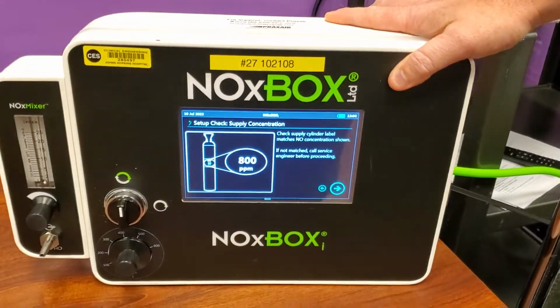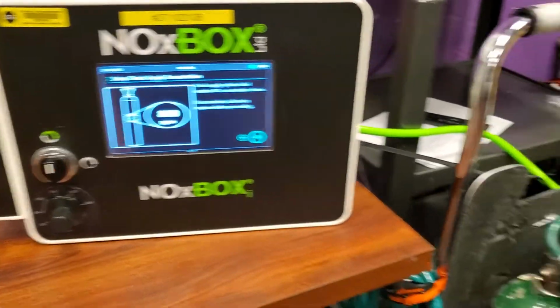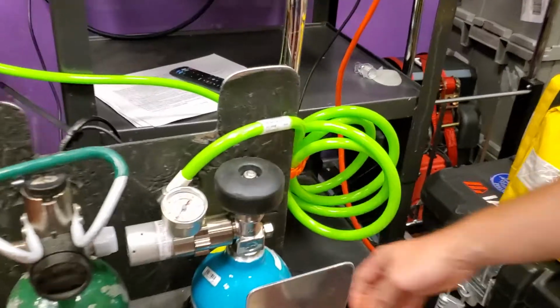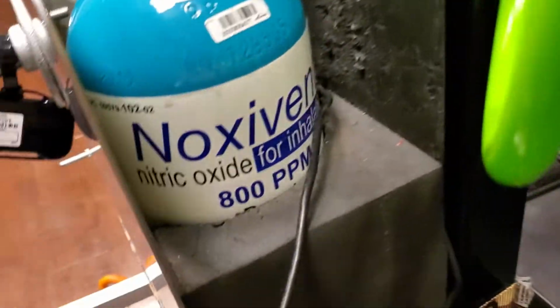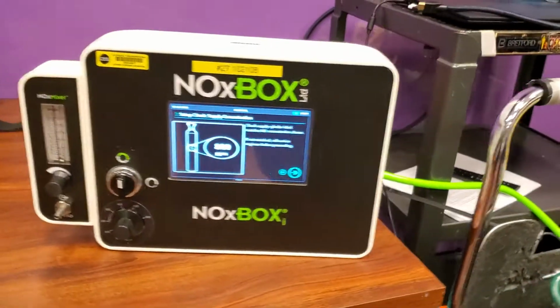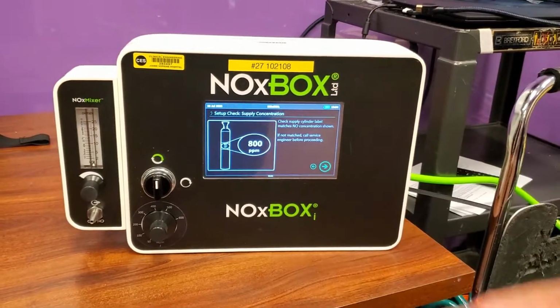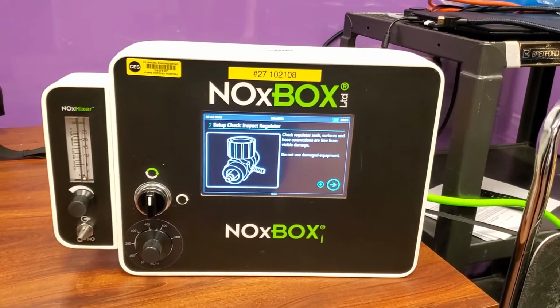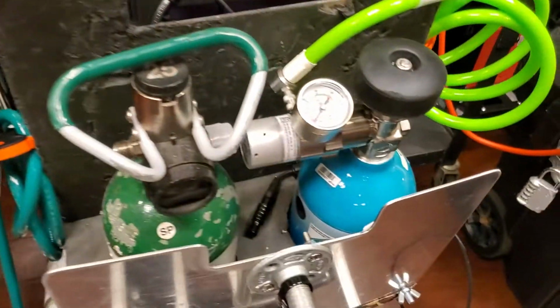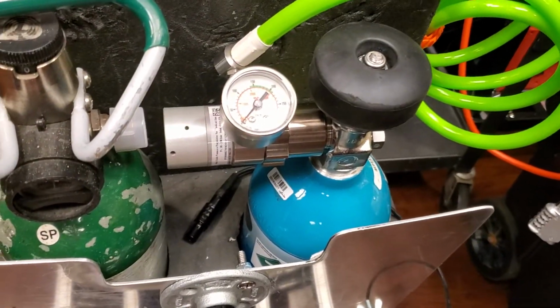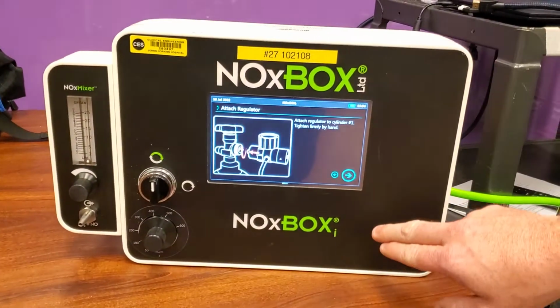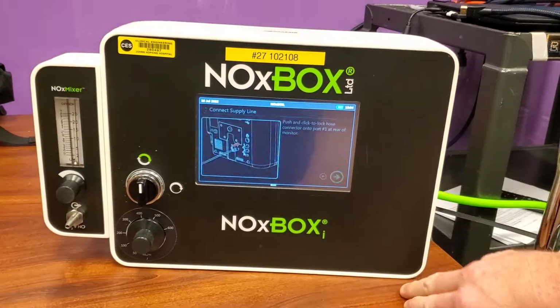Next up, we're going to be checking the concentration of our bottle here. So on the side here, we can see that it says 800 parts per million. That is the only available one from this company, so it should always be that 800 parts per million. So we'll go to our next page here. Next, we're going to inspect the regulator. We're always going to have our regulator already attached to it, but just make sure your connections are tight, make sure everything's good there. It's already attached there.